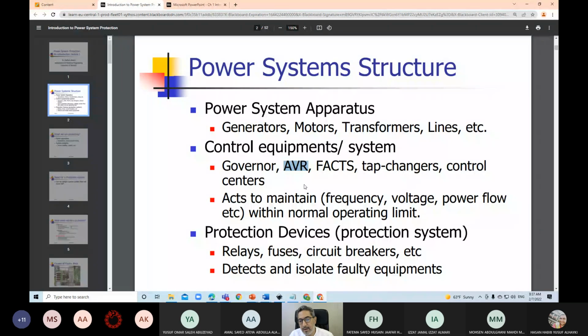So we use a control system, a closed loop system. We compare the voltage at the terminal of the generator with a setting, and we want this voltage to be maintained by changing the excitation of the synchronous generator. We have external FACTS devices. I assume that you have taken one of the elective courses in flexible AC transmission systems or controllers. It could be STATCOM, it could be series compensation devices. So there are different types of FACTS controllers. We can use tap changers in the transformers to change the transformer ratio so that we maintain the voltage using the tap changer of the transformers.